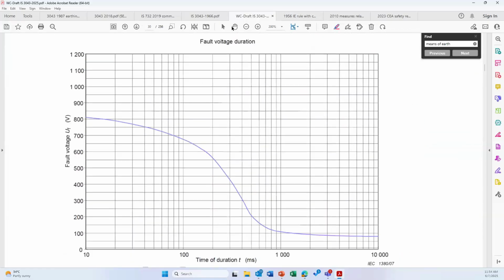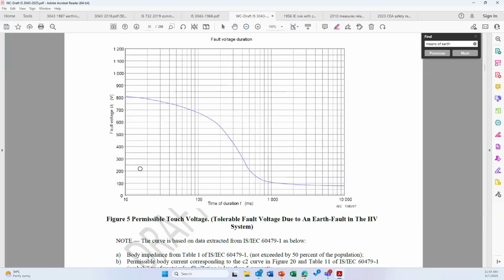Then finally, you have a graph like this. So this is the permissible touch voltage with respect to time. You can see here time, the duration of the fault disconnection time as well as the fault voltage. So always the idea is the touch voltage has to be lesser than this within the tolerable limit. Means if the disconnection time is 100 millisecond, then the maximum allowed potential is, let's say, something about 750. If the disconnection time is something about 1 second, maybe the voltage is something about 100 volt.